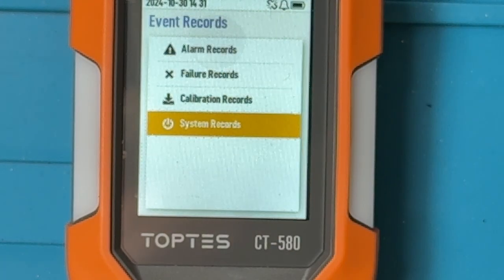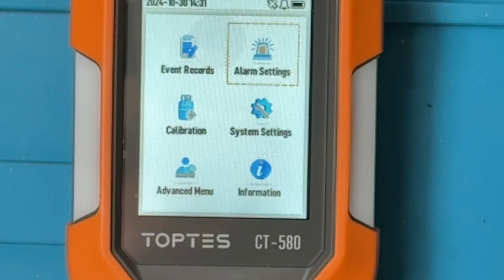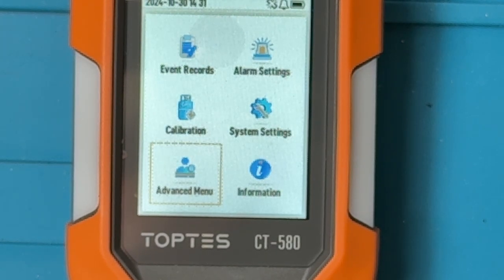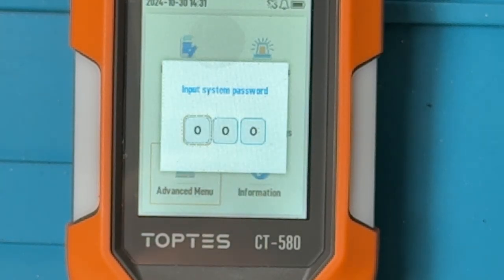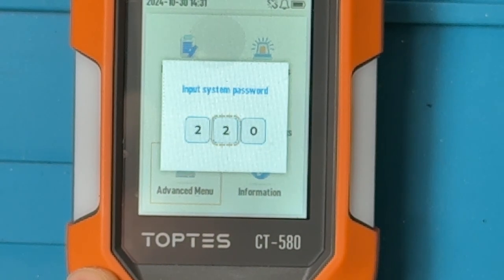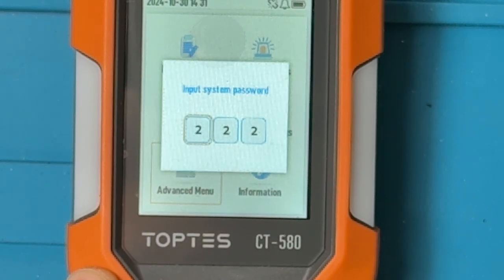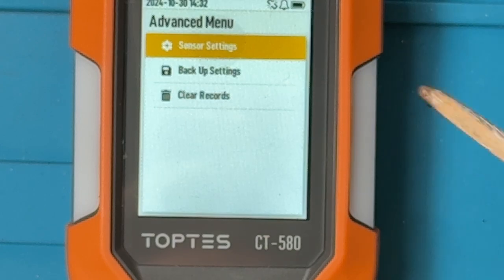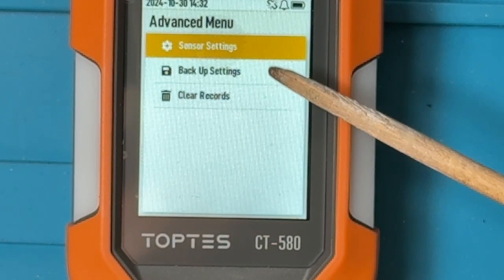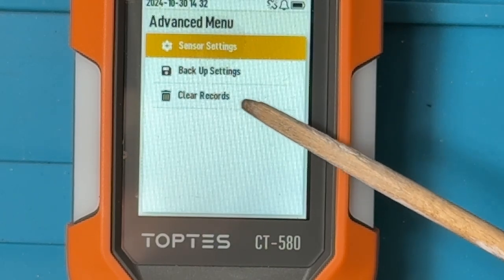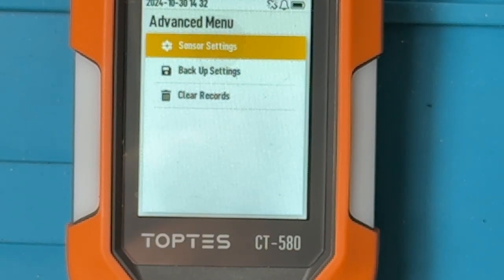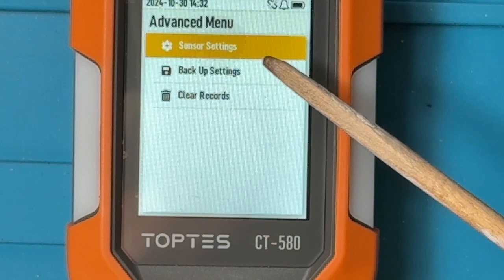So we've looked at all the records. If we go now to the advanced menu, and of course that one's a password, there is a default password for the unit, which happens to be 222. We have the advanced menu, and in the advanced menu we see we have sensor settings. We can back up settings and clear records. Let's have a look at the sensor settings.